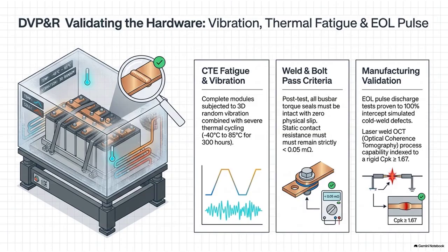And while the pack is soaking at these extremes, they subject it to massive dynamic loads. They utilize industrial battery cyclers to inject violent 600-amp current pulses into the pack, simulating repeated maximum torque acceleration events. Just flooring it over and over again. Exactly. And while this is happening, laboratory-grade instrumentation is independently recording the true physical internal resistance.